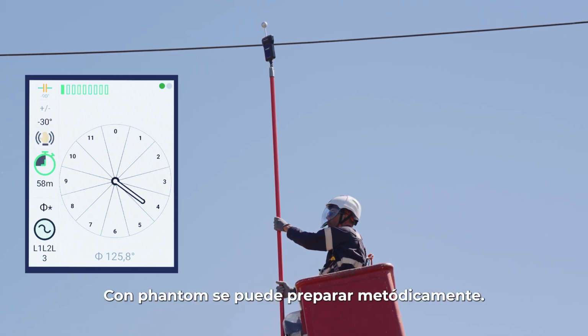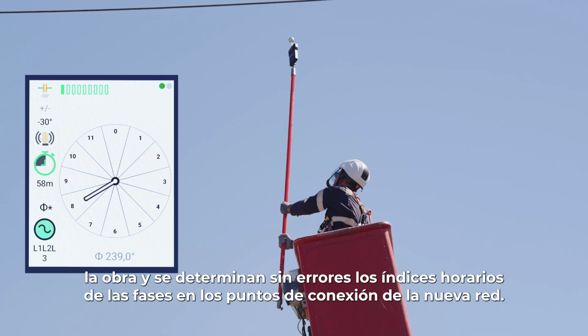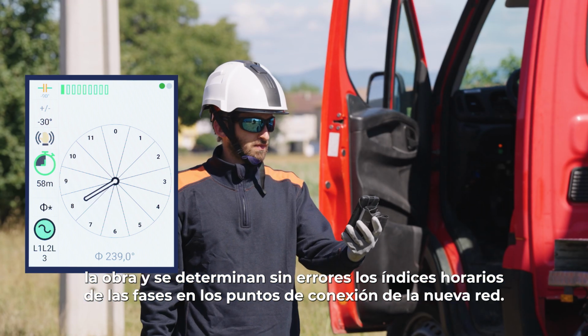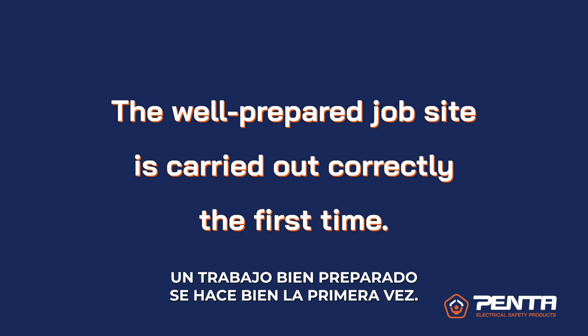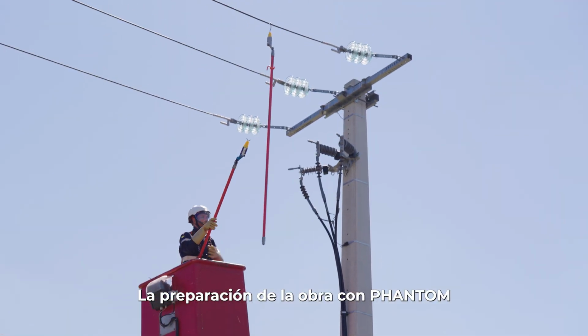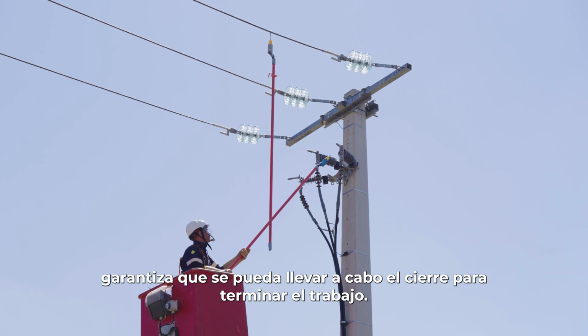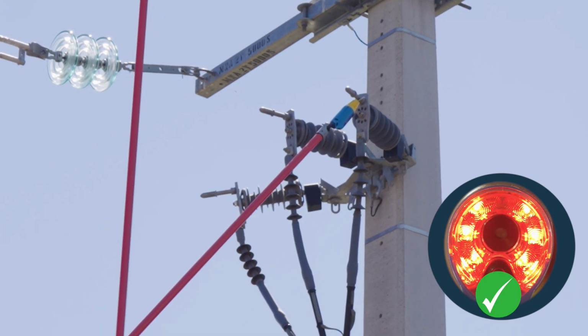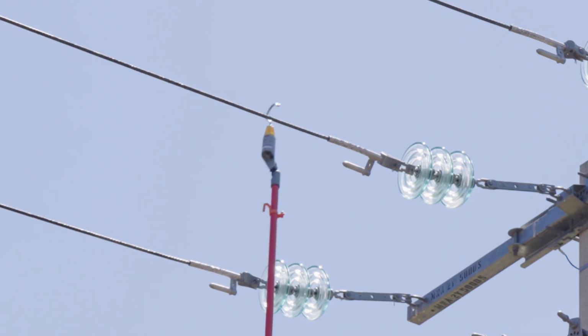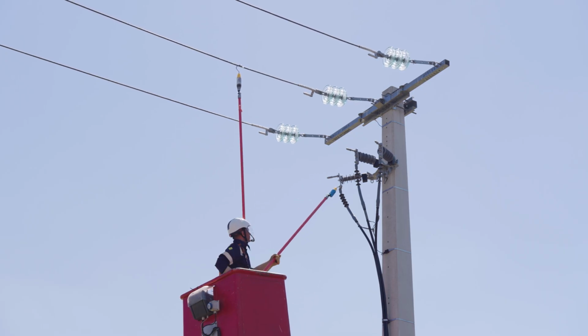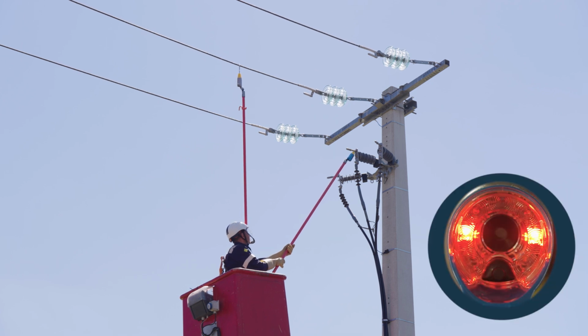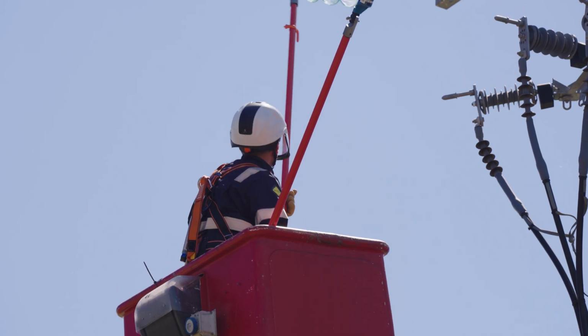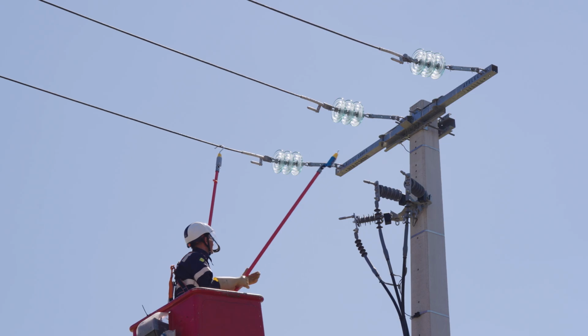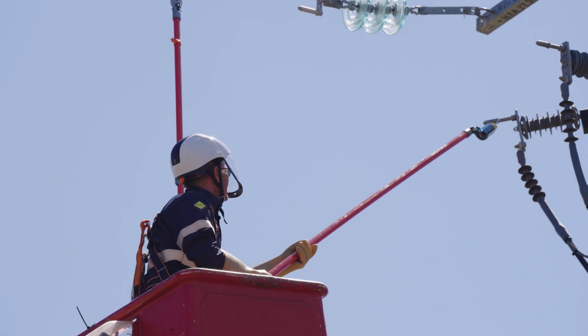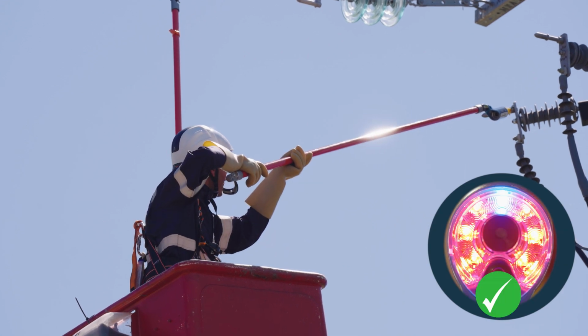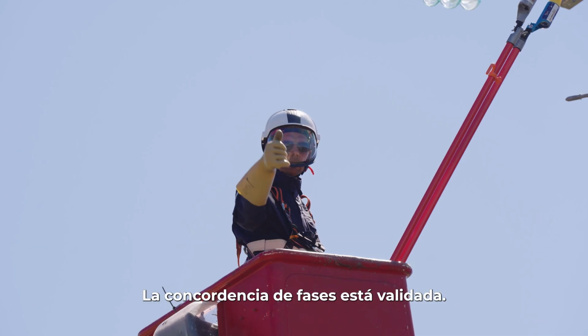With Phantom, the restructuring project can be methodically prepared. The hourly index of the phases at the connecting points of the new network are determined without error. Preparing the job with Phantom ensures that the closure can be carried out to complete it. Phase concordance is validated.